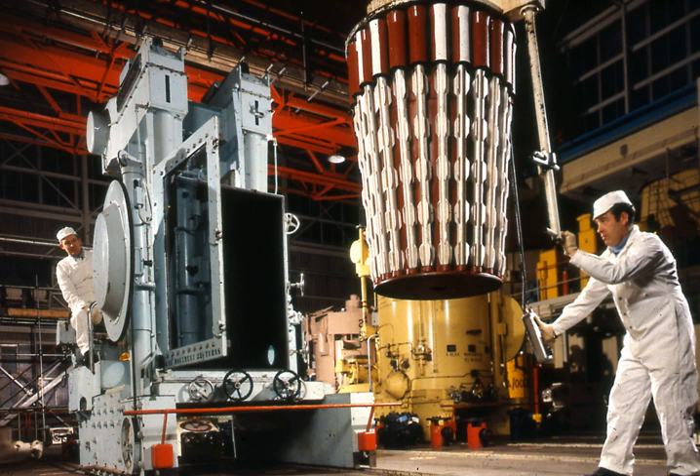As there was no water in the core, and thus no possibility of a steam explosion, the building was able to tightly wrap the pressure vessel, which helped reduce construction costs. In order to keep the size of the confinement building down, the early Magnox designs placed the heat exchanger for the CO2 gas outside the dome, connected through piping. Although there were strengths with this approach in that maintenance and access was generally more straightforward, the major weakness was the radiation emitted particularly from the unshielded top duct. The Magnox design was an evolution and never truly finalized, and later units differ considerably from earlier ones.